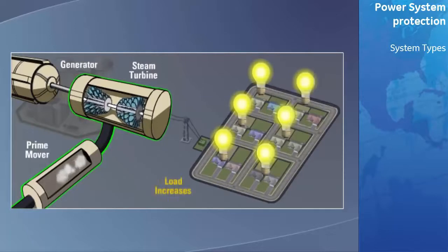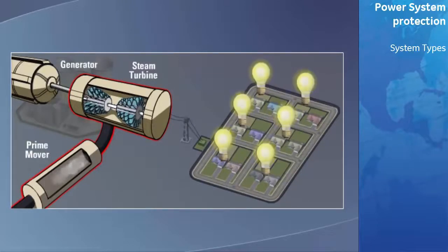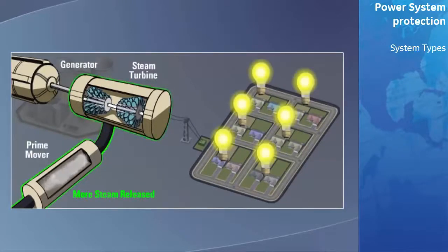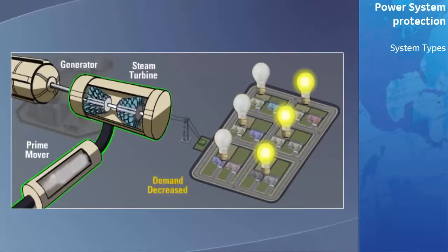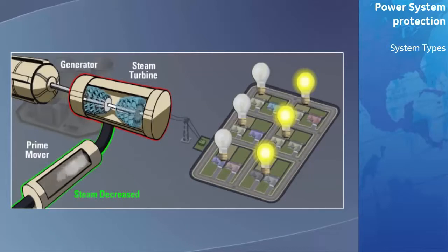As the load increases, the generators would tend to slow down, resulting in a reduction of output voltage and frequency. The generator's control system will sense this and input more mechanical energy to match the increased load. If the demand decreases, the generator will speed up, and the control system senses this and then takes appropriate action to reduce the mechanical energy input into the system.